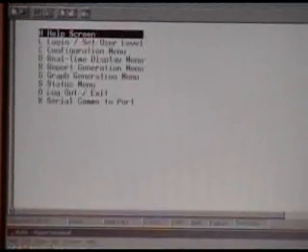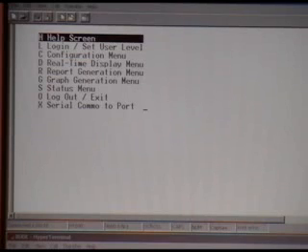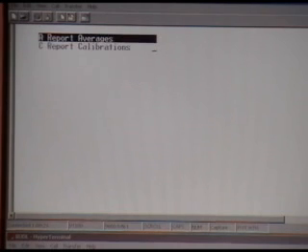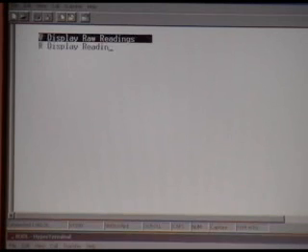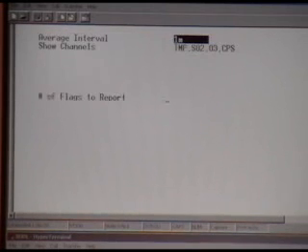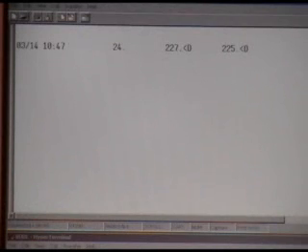To watch what the minute averages are and record them, we go to Real-Time Display, D. Hit C, Continuous Average. We don't want the SO2 channel that was here at one time. We just want temperature, ozone, calibrator, and then hit enter, and it'll give you your minute averages.